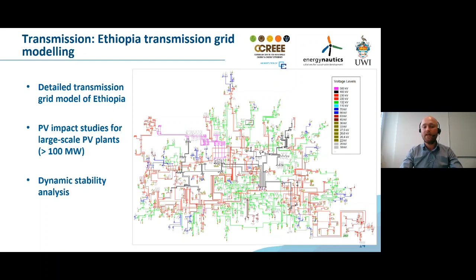This was also an example from a recent study where we looked at the impact of new large-scale PV power plants, in the order of 100 to 150 megawatts, and what the impact would be, doing this analysis with DIgSILENT PowerFactory.